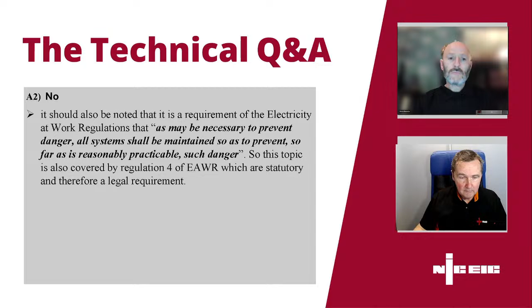Another one. During a consumer unit replacement, a borrowed neutral is found between the upstairs and downstairs lighting circuit, which regulation prohibits this? So we had an engineer asking on a domestic, because they were doing a periodic inspection of the domestic installation and wanted to know what they should do, and were quite old school in that they didn't want to put an observation down unless they could put a regulation against it, which is good practice.